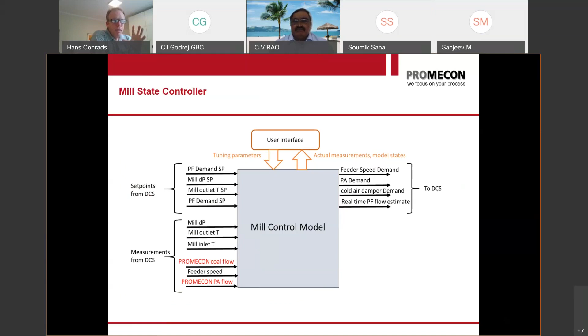What does that mean for your mill? Let me show you two slides. First, when you start your mill, look at your mill output demand - this is the lowest signal, and it goes up step by step. Now, when you try to get the real-time value close to that, look at how your feeder rate will have to overshoot in order to reach it. So your feeder will be controlled differently than it is today.